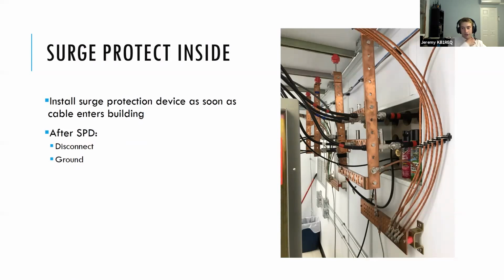So once we come inside with our surge protection, what's our strategy in there? When we talked about our SPDs earlier, those are our isolation devices. Those disconnect and try to cut off those undesired paths for the surge. We want to install those as soon as your cable comes inside, so as early as you can. The standards have various lengths that they state, but essentially, as soon as practical once it's inside, you want to surge protect it.